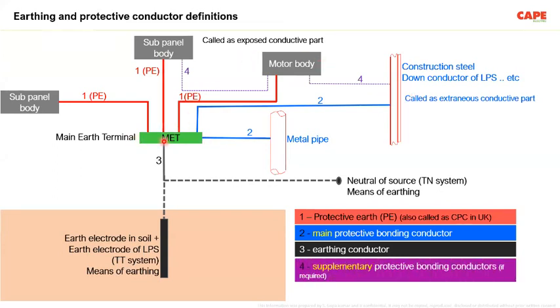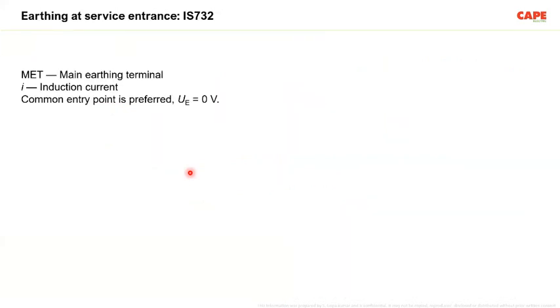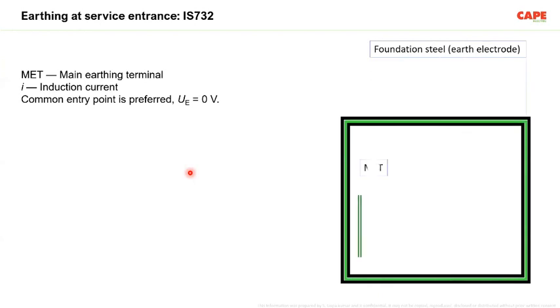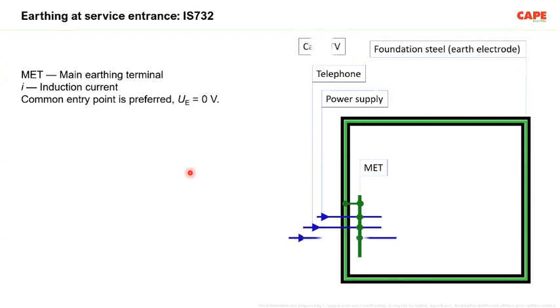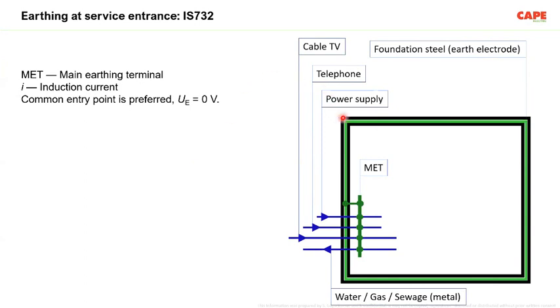Protective equipotential bonding is created by interconnecting various exposed and extraneous conductive parts in the building. You have an MET, a big bus bar, which is the zero reference of the whole building, and all the metallic exposed and extraneous parts must be connected to this bus bar. The bus bar is connected to an earth electrode in case of a TT system, and to the neutral of the source in case of a TN system. This whole thing together is called protective equipotential bonding. So protective earthing means you should connect your motor, or your class 1 apparatus, to your protective equipotential bonding. That is called protective earthing. It has nothing to do with the earth electrode in soil. In IS 732, picture number 68, I believe, you can see this kind of picture. What does it mean? You have a building.